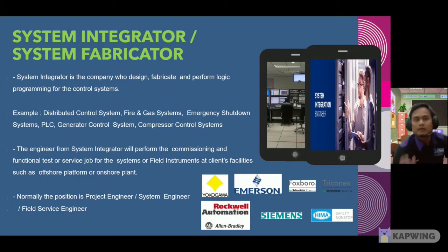Lastly, for system integrator and system fabricator, for this career, instrument, the system integrator is the company who designs, fabricates and performs logic programming for the control system. For example, a distributed control system, fire and gas system, emergency shutdown systems, PLC, generator control system, compressor control system. The engineer for the system integrator will perform the commissioning and functional test.